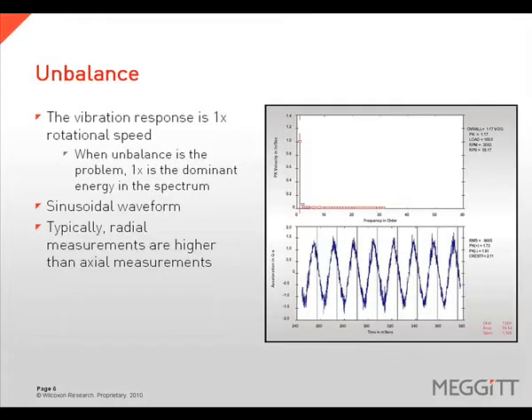When imbalance is the problem, the vibration response will occur at 1 times rotational speed, and 1 times is the dominant energy in the spectrum. The waveform will be sinusoidal, and typically the radial measurements are higher than the axial measurements.